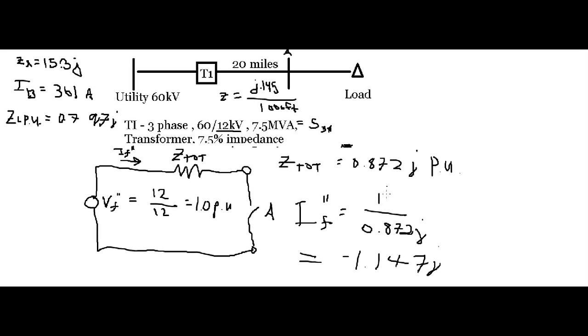And finally, we can use all the values that we calculated in order to solve for the short circuit current. So all we're going to do for that is take our I fault per unit current, and also remember that I per unit is equal to I actual divided by I base. Here, I'll write it up here. This is also an equation out of the Grainger textbook.